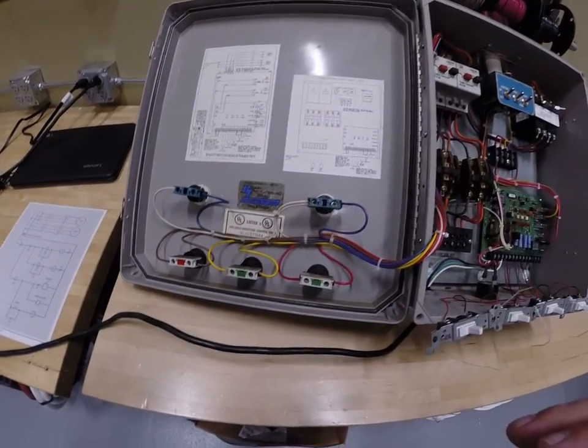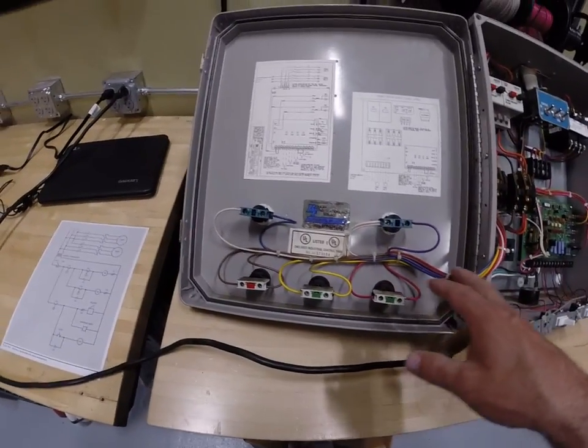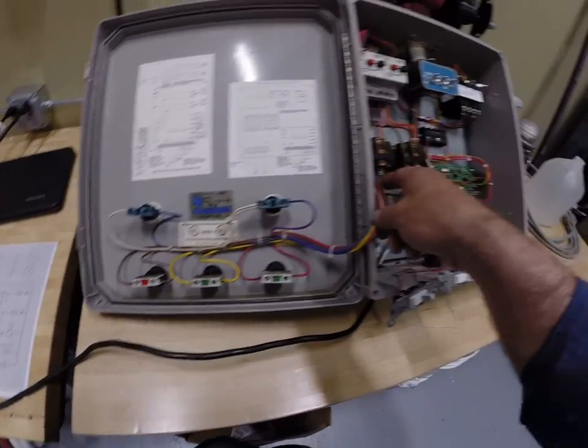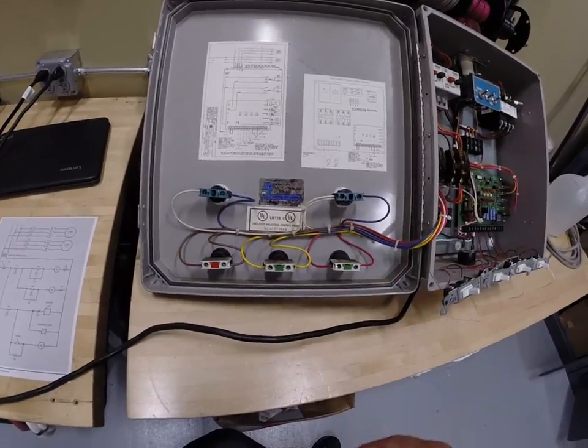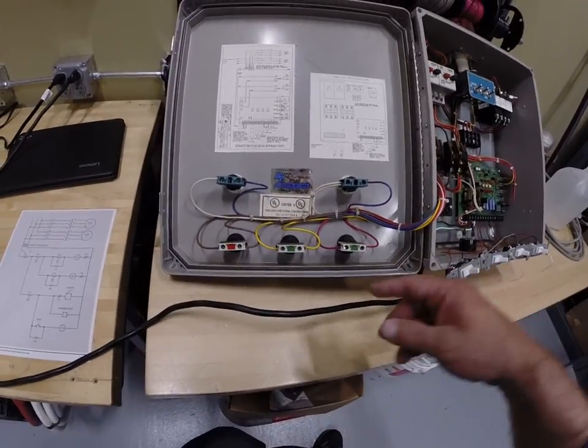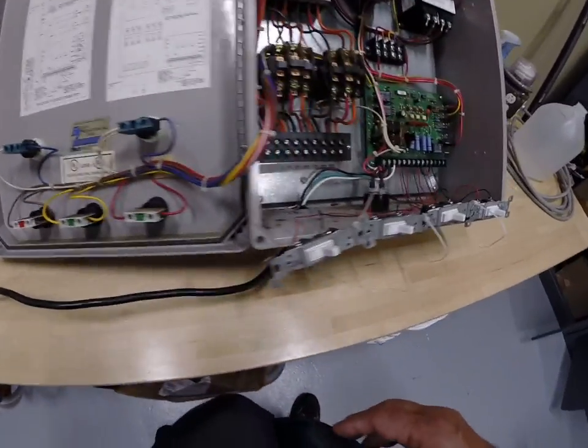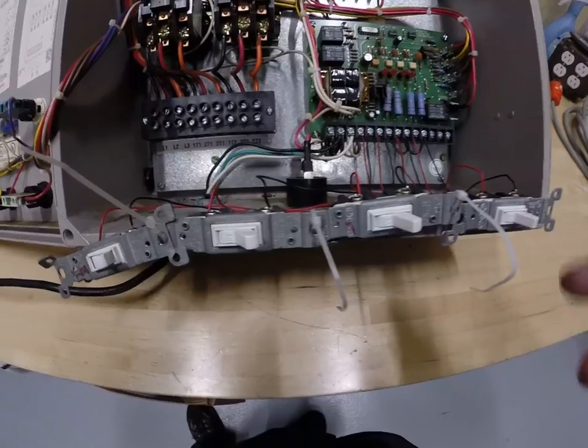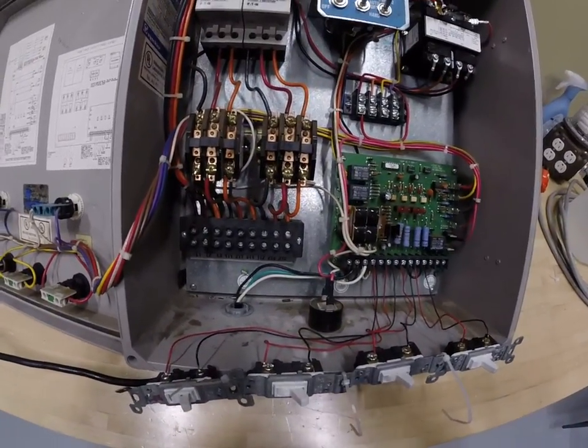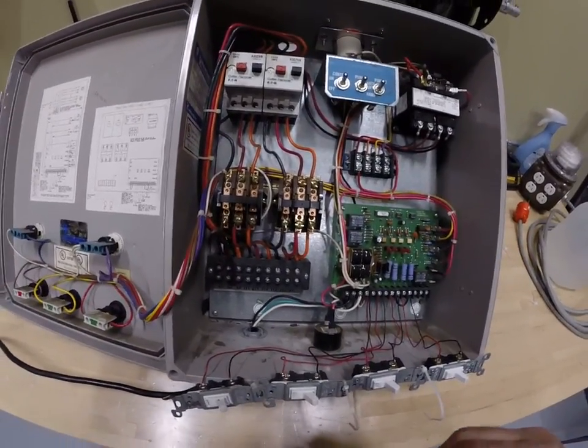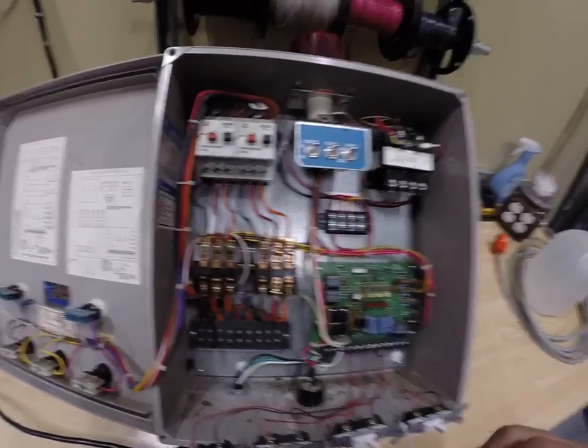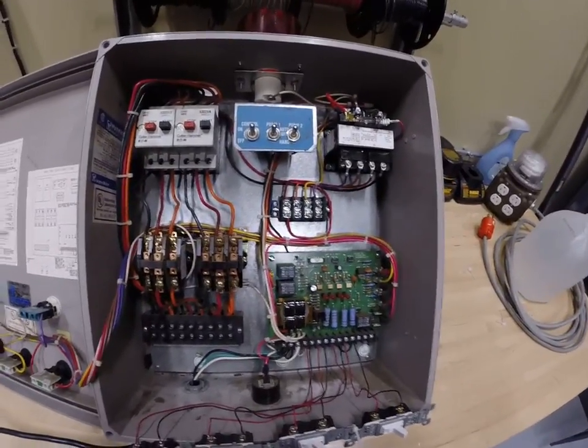You can certainly test this to make sure your stuff is running. But the cool thing about this circuit is this is an actual circuit that was used in the field. An actual board that was yanked out of the field. All the components are pre-wired. You can see how they left a nice little bit of slack so you can open up the panel to the code minimum 90 degrees. This actually goes 180 degrees, which is even better. Somewhat neatly tied in. Like I said, I just modified the circuit so I could run it.